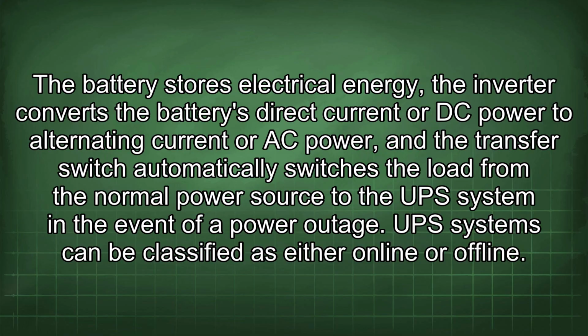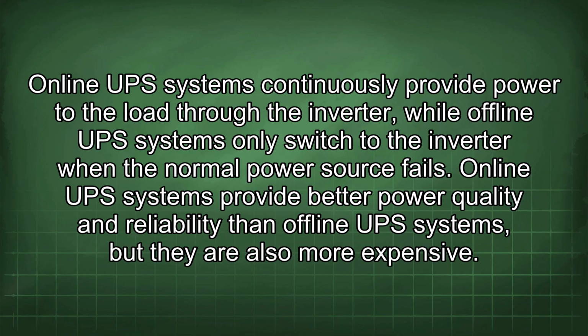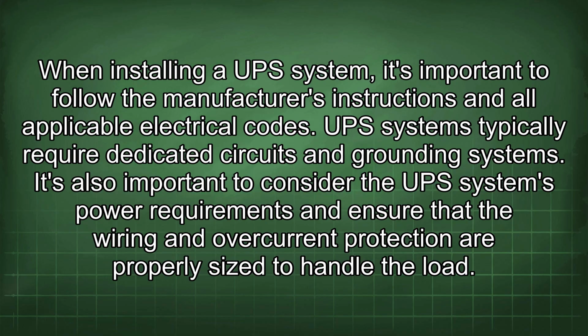UPS systems can be classified as either online or offline. Online UPS systems continuously provide power to the load through the inverter, while offline UPS systems only switch to the inverter when the normal power source fails. Online UPS systems provide better power quality and reliability than offline UPS systems, but they are also more expensive. When installing a UPS system, it's important to follow the manufacturer's instructions and all applicable electrical codes. UPS systems typically require dedicated circuits and grounding systems. It's also important to consider the UPS system's power requirements and ensure that the wiring and overcurrent protection are properly sized to handle the load.